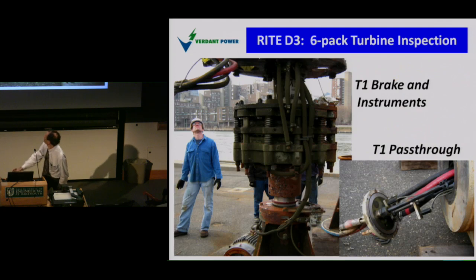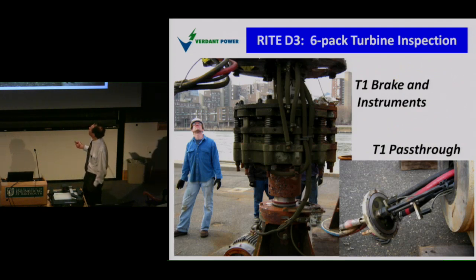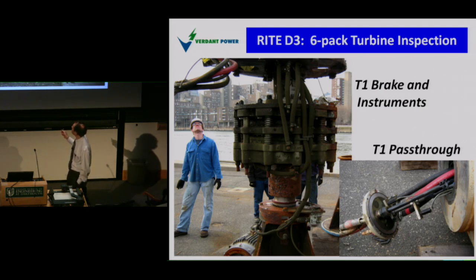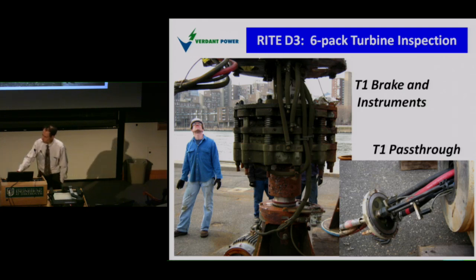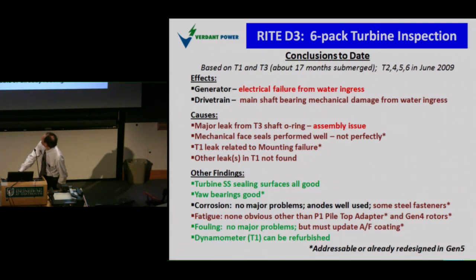These are the insides of turbine number 1. This is the brake. You can see it's covered with brake dust. It gives you a sense of how much braking it was doing. And this is where the water cooling hoses and the instrumentation, and these are water detectors, comes out of the turbine. And we expect to put the dynamometer back into service. This is the torque sensor up here. So here are some of the results of the findings on tearing down and inspecting turbines 1 and 3.